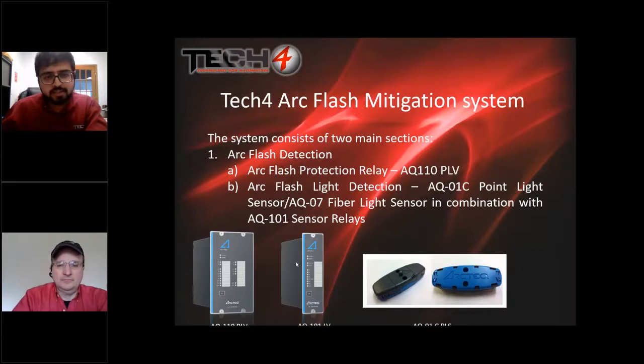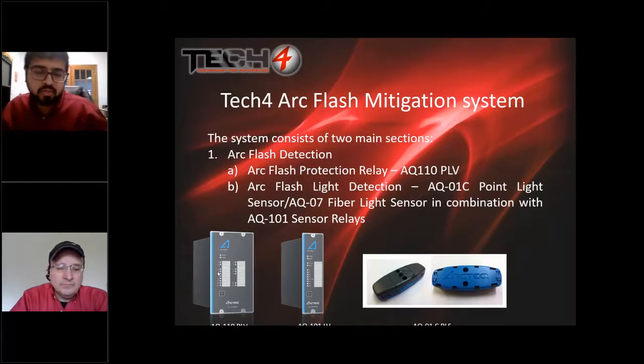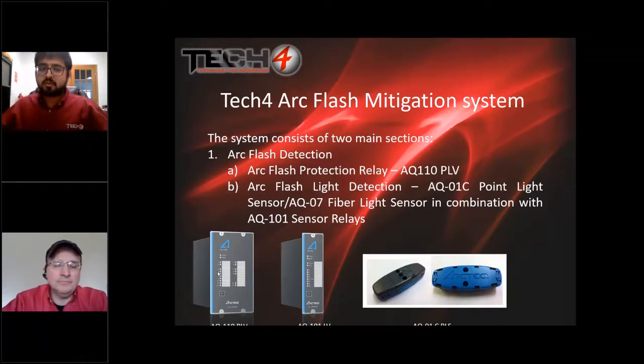The sensor relays themselves, the AQ101, are just light detection, and they can be placed up to, I think, 3,000 feet away, in a different building where you want to still protect your downstream assets and downstream equipment. It shares the light back to the AQ110, and it also sees the current, so it sends a trip signal to the AQ1000 arc quenching device, and it quenches. And all of this takes place in less than 4 milliseconds. And let me go to the quencher slide to explain more about that next.